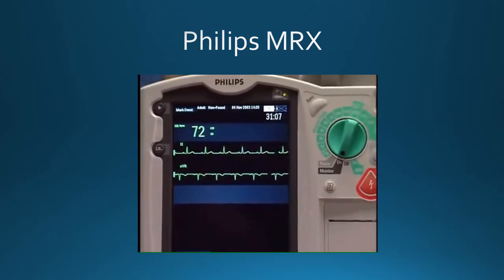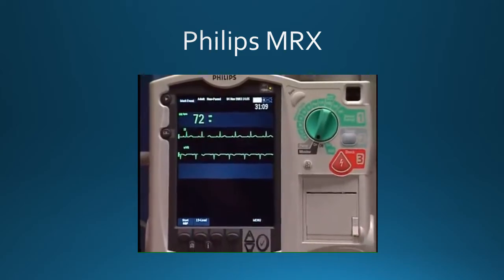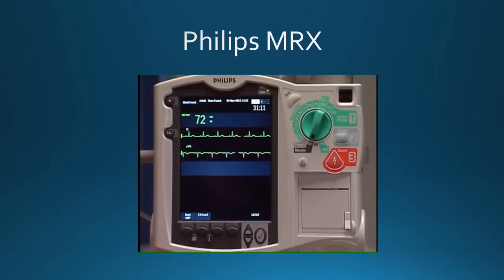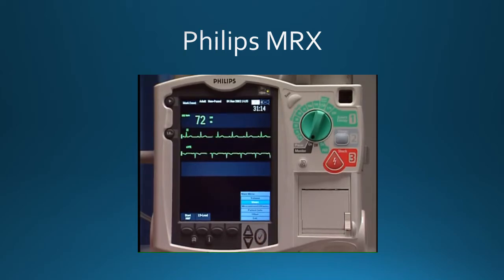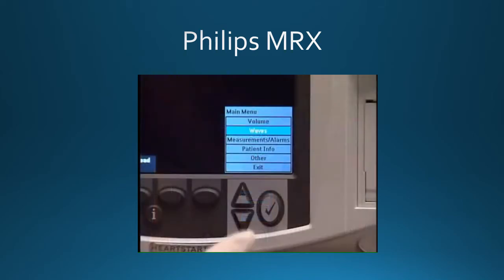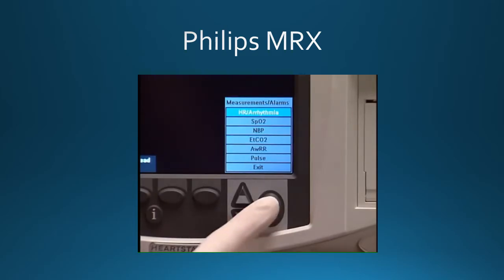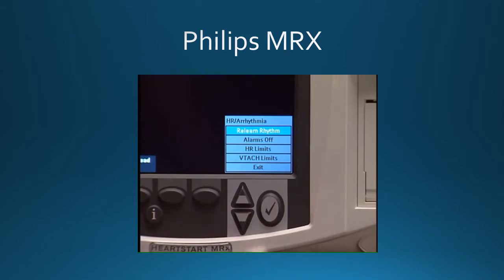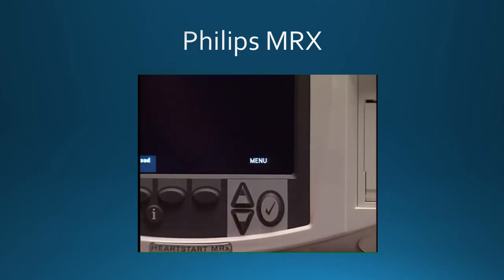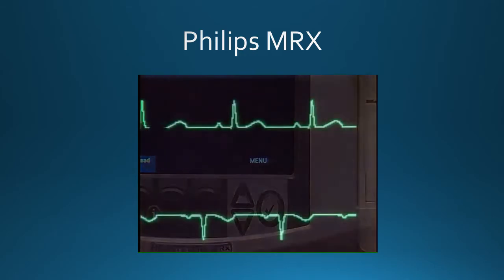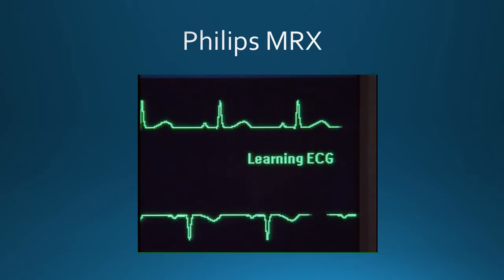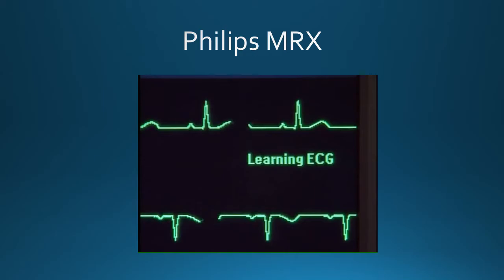If the device is not identifying the patient's rhythm correctly, you need to initiate relearning. To do this, press the Menu Select button. Navigate to Measurements, Alarms, and then HR Arrhythmia. Select Relearn Rhythm and press Menu Select. The MRX will then display a message confirming that manual relearning has begun.